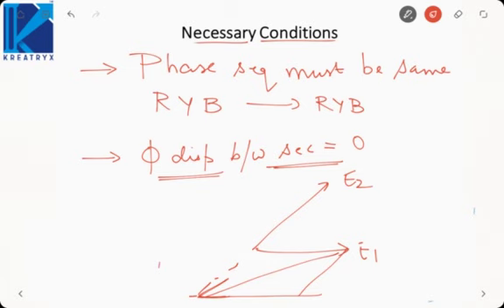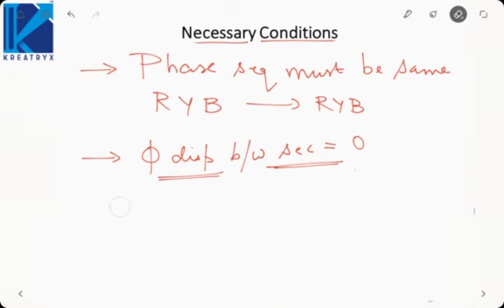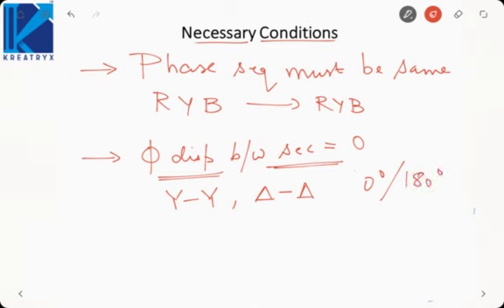So in case of three-phase transformer, we should connect those transformers in parallel which provide the same phase shift between primary and secondary. That is, star star and delta delta can be connected in parallel because both provide 0 degree or 180 degree phase shift. Or we can connect star delta and delta star transformer because both provide plus minus 30 or plus minus 150 degree phase shift. But we cannot connect star star and star delta in parallel because phase shift of both the transformers is different. So secondary voltage will never have the same phase, hence there will be circulating currents. Okay, that is why it must be kept in mind that the phase sequence as well as phase shift of both the transformers must be equal.